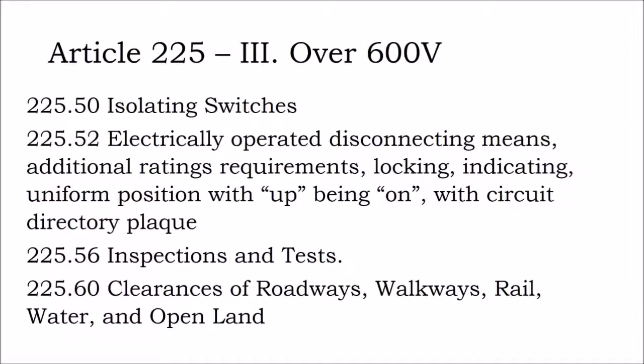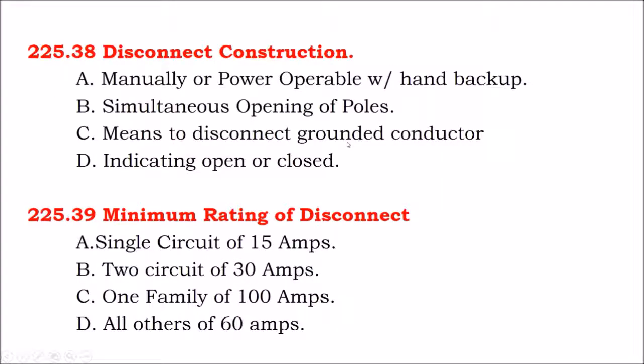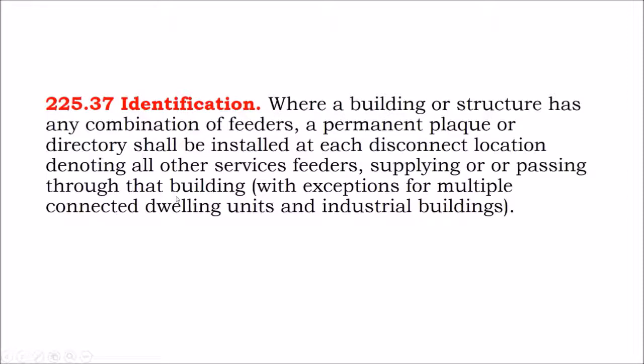We have 225.52, electrically operated disconnecting means, additional requirements, including an indicating switch on the directory plaque. Sometimes, like the requirements for the knife switch disconnect at the residential level, that knife switch disconnect is not part of code, but often the inspectors are treating your residential arrays kind of like distributed power systems, and they're used to seeing knife switches on distribution stations and substations, and so they like to see them on your solar array as well.